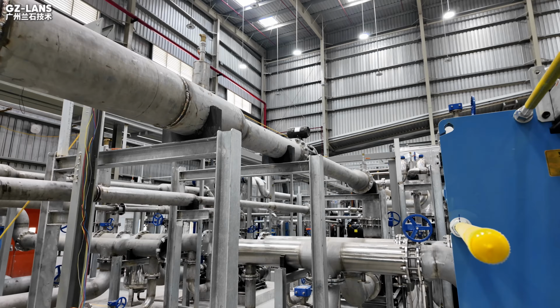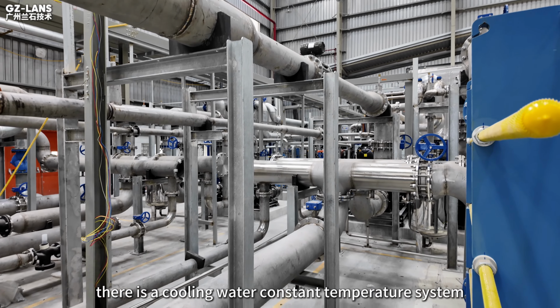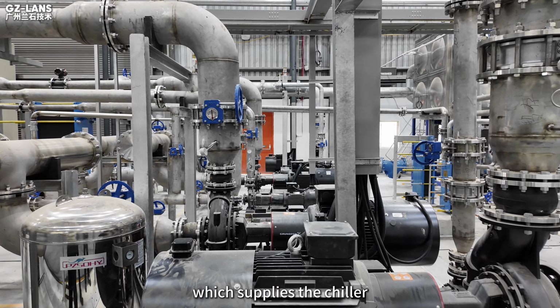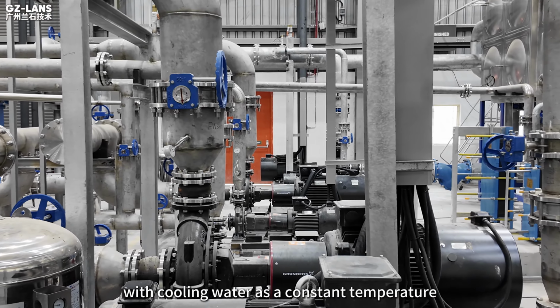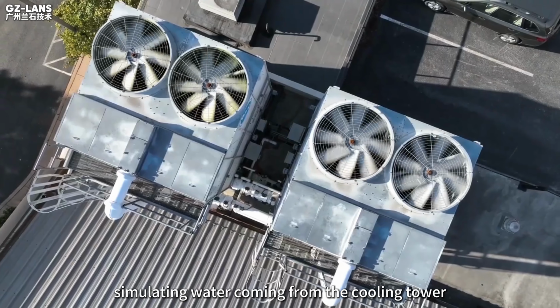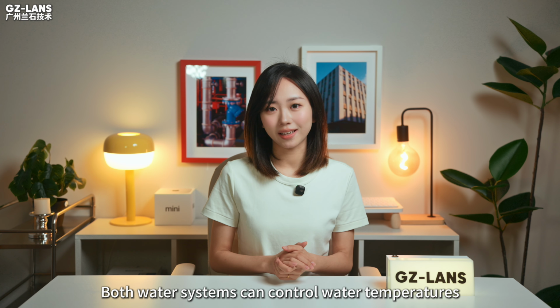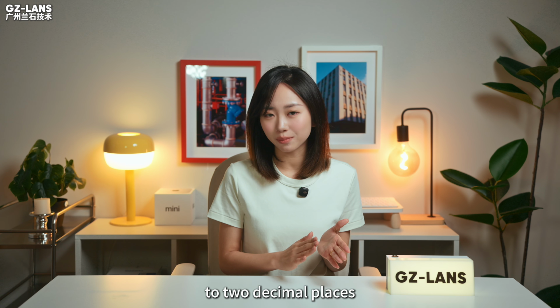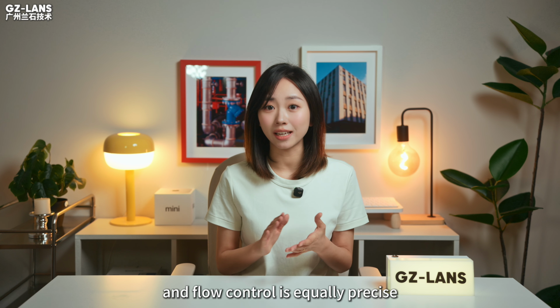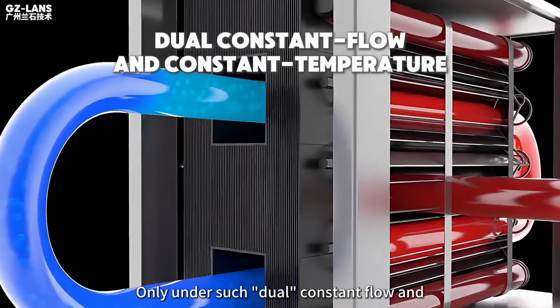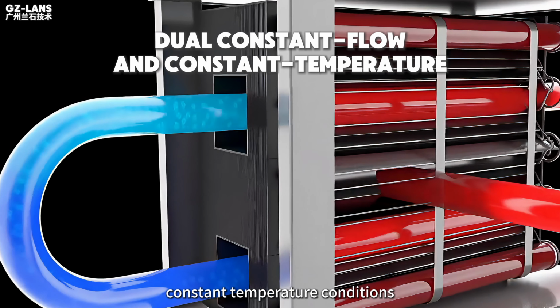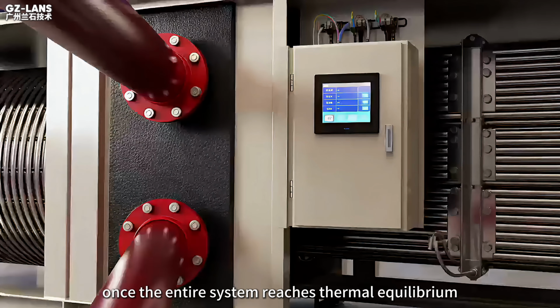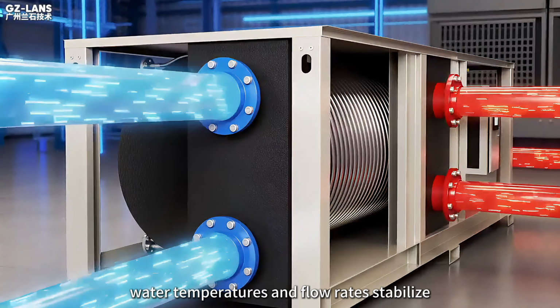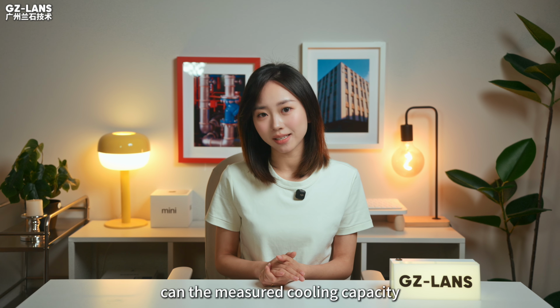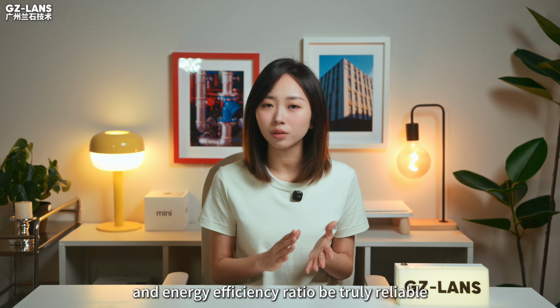On the outdoor side, there is a cooling water constant temperature system, which supplies the chiller with cooling water at a constant temperature, simulating water coming from the cooling tower. Both water systems can control water temperatures to 2 decimal places, and flow control is equally precise. Only under such dual constant flow and constant temperature conditions, once the entire system reaches thermal equilibrium, water temperatures and flow rates stabilize, can the measured cooling capacity and energy efficiency ratio be truly reliable.